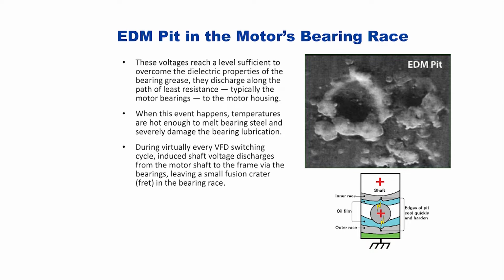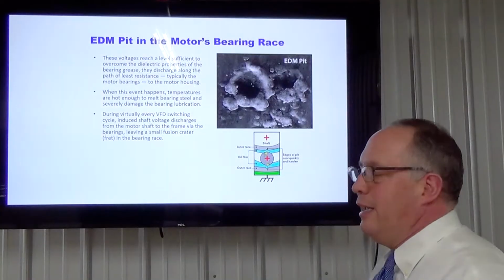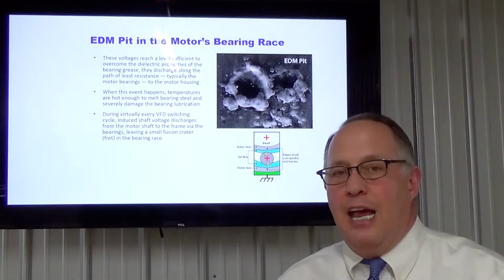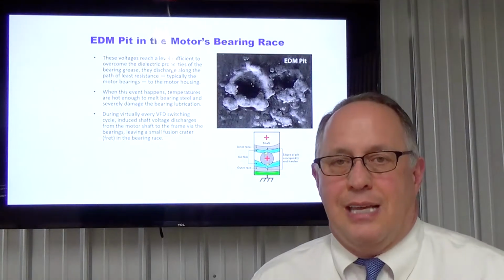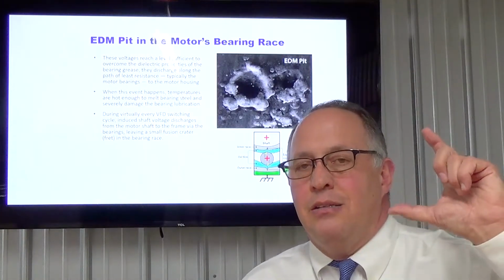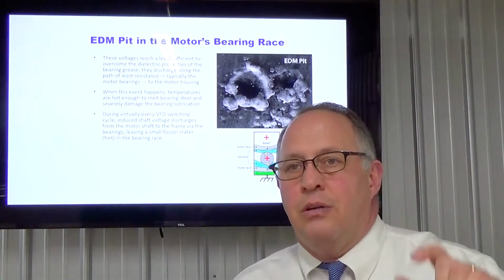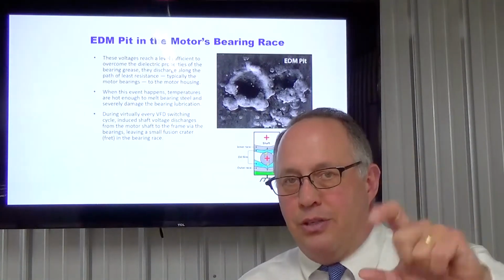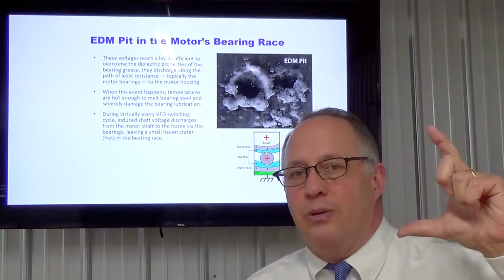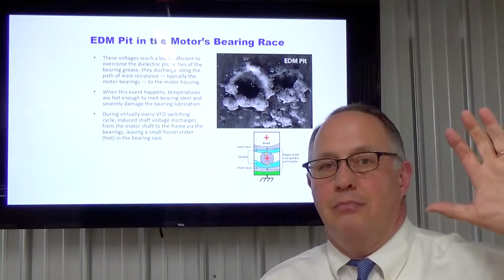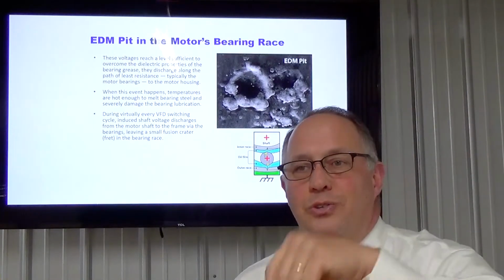During virtually every VFD switching cycle, induced shaft voltages discharge from the motor shaft to the frame via bearings, leaving a small fusion crater in the bearing race. In other words, this isn't happening every once in a while. This is happening every single cycle. Hundreds, thousands. Depending on high frequency, it can happen a million times and cause these little pits.